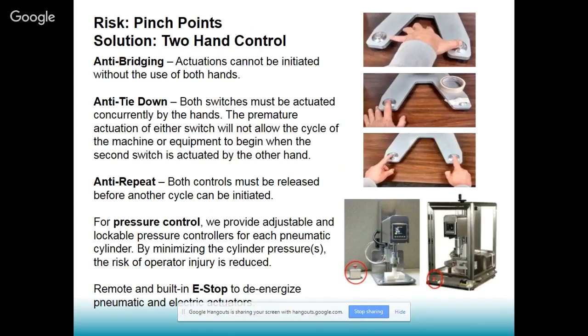With the anti-tie down, we have logic in the programmable logic controller that monitors the start switches. So if an operator would tie down one of the switches, it might work for the first cycle, but it will definitely not work for any of the successive cycles. Also, there is a 500 millisecond delay that is a window of opportunity for the operators to start the test. If they don't press two push buttons within 500 milliseconds, the test will not start.